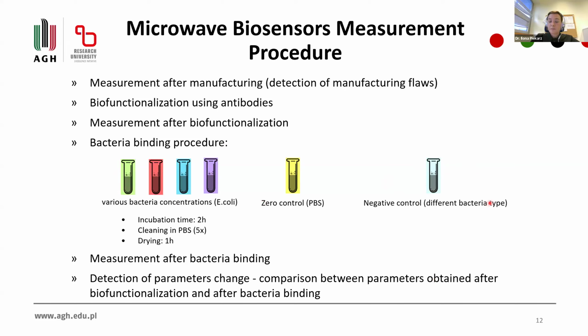All of those bacteria are suspended in PBS, that is phosphate buffered saline. So we also need to know the reference, so how the sensor responds to pure PBS. That is our zero control. So we divide the sensors into some groups, put one group into, for example, 10 to the power of 4 colony forming units per milliliter of the bacteria, another one into 10 to the power of 3 colony forming units per milliliter, and so on. We can go as low as our biotechnology department can prepare for us the test tubes with the bacteria.